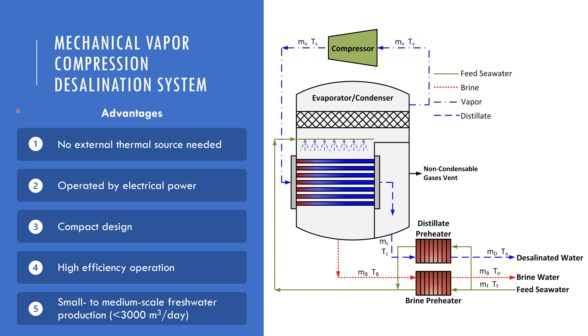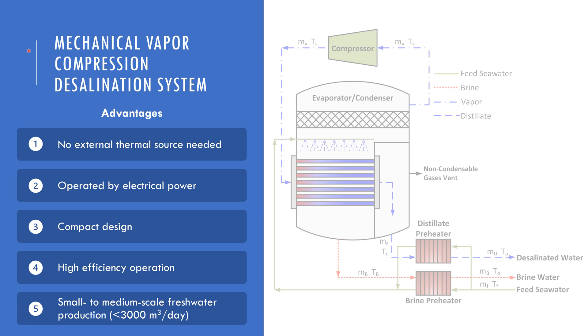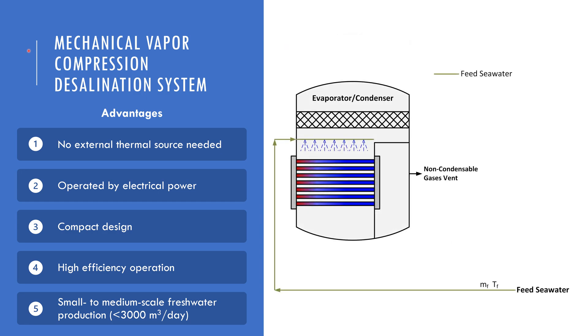The mechanical vapor compression desalination system, or MVC for short, shown here on the right, offers several advantages over other thermal desalination processes. The first step in this process is to pump the feed seawater to the spraying headers. Inside this heat exchanger, called a horizontal tube falling film evaporator, the sprayed seawater forms a falling film that trickles down the tube bundle, absorbing thermal energy and partially vaporizing. The formed vapor rises, passing through the mesh and out of the evaporator. The sprayed seawater that did not vaporize falls to the brine basin at the bottom of the evaporator to be discharged from the system.